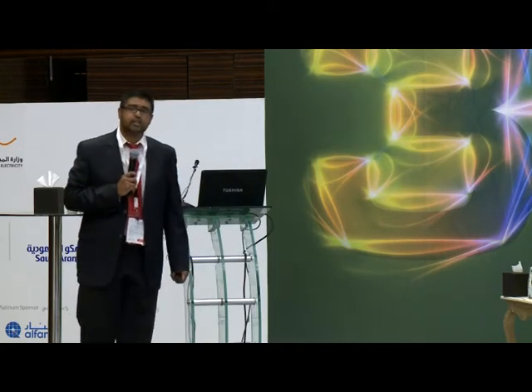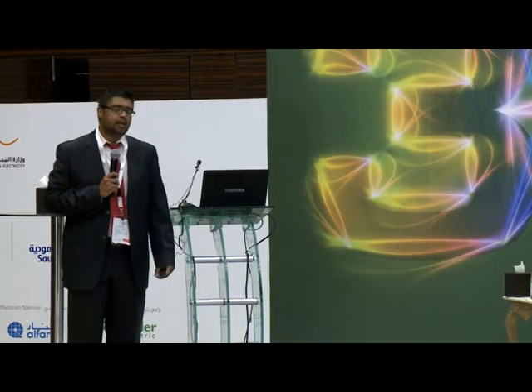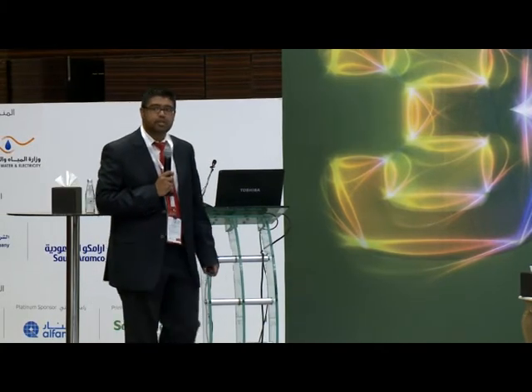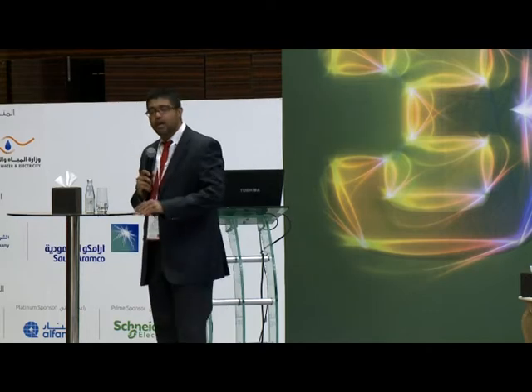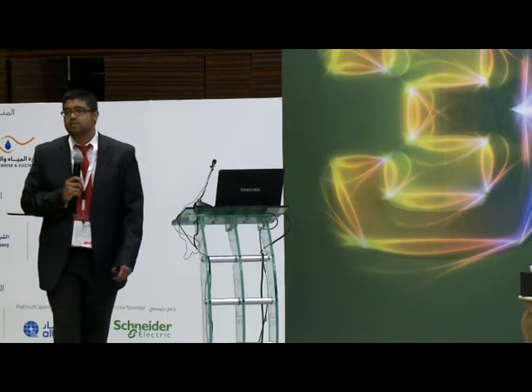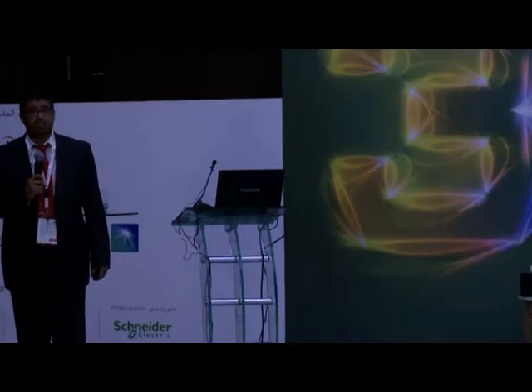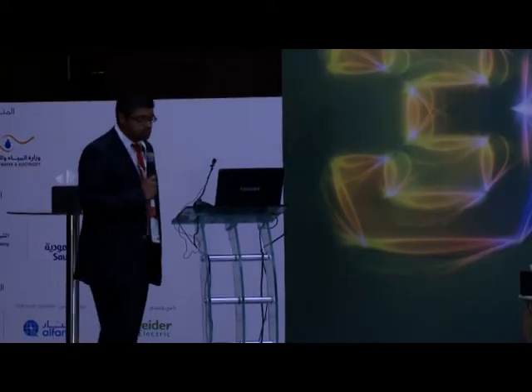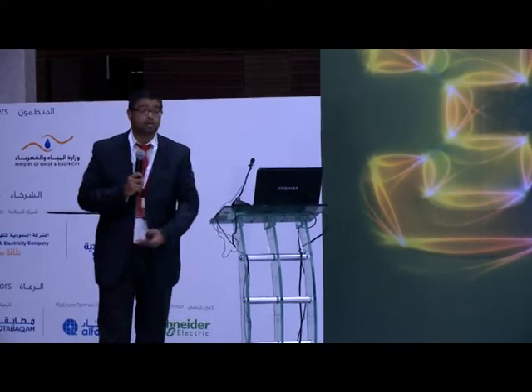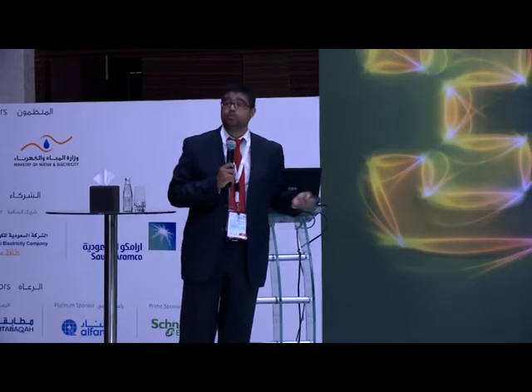Let's first start off with statistics, because statistics are important to convince the audience about the reality of electrical arc flash safety. Dr. Mary Capelli-Schellpfeffer, in an IEEE paper, studied EDF, the electricity distributor of France, and over a 10-year period, she studied 120,000 workers. And of that 120,000 workers, what she found was, on average, we had 125 incidents per annum. And of that 125, 77% of them contained an arc component. That's a very scary number, 77%. Of those, 21% were disabling injuries. That meant a person would lose an arm, would lose a limb, probably will have psychological trauma and would not be able to resume their normal work functions. And 2.4% of those were fatalities.